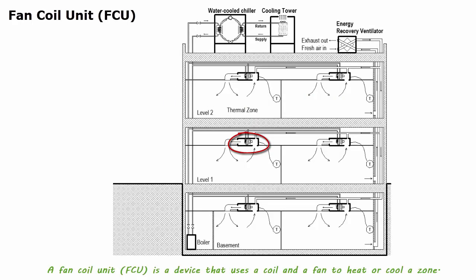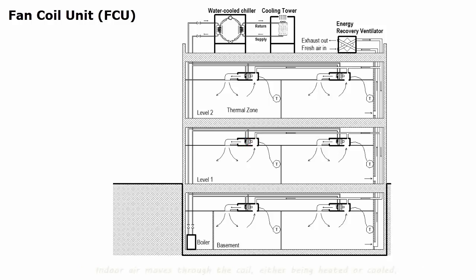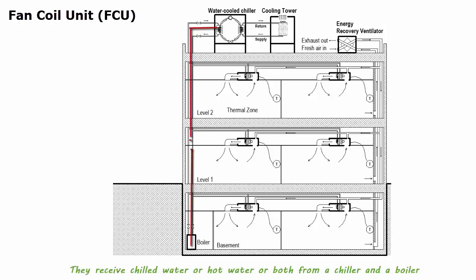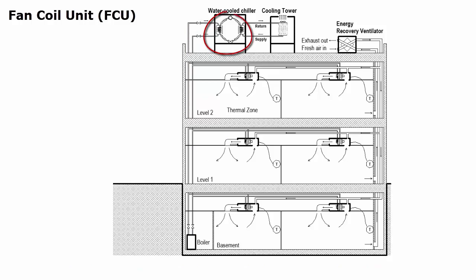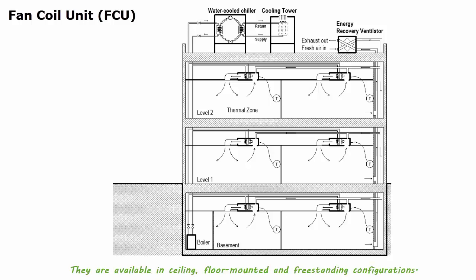A fan coil unit is a device that uses a coil and a fan to heat or cool a zone. Indoor air moves through the coil, either being heated or cooled, and then back to the room. Fan coil units are essentially small-scale air handling units installed throughout the building. They receive chilled water or hot water or both from a chiller and a boiler without extensive ductworks. They're available in ceiling, floor-mounted, freestanding configurations. Fan coil units are typically less expensive to install than duct systems.